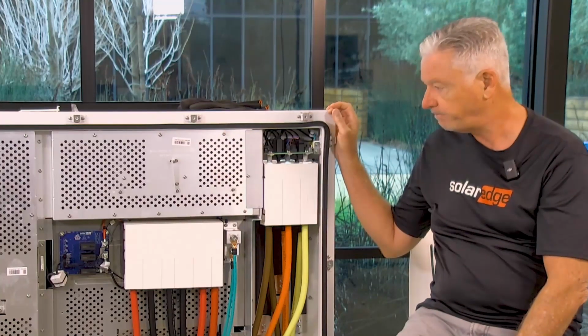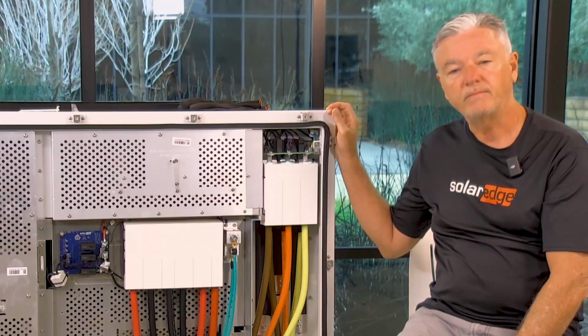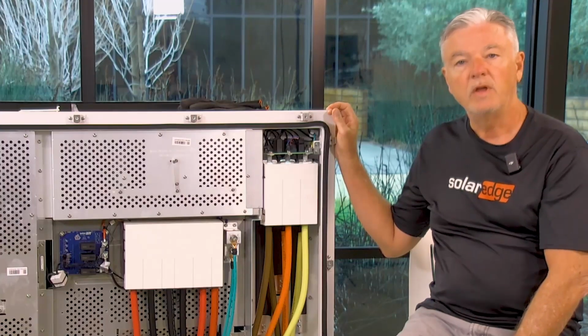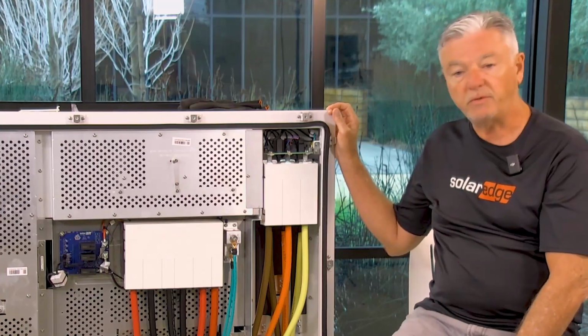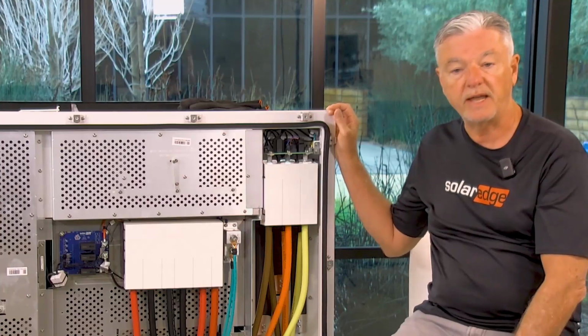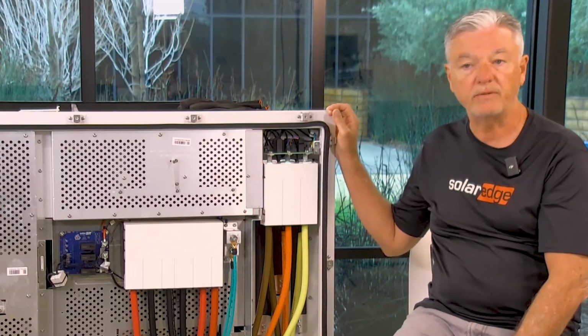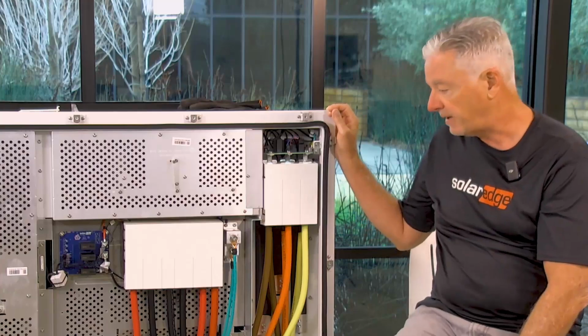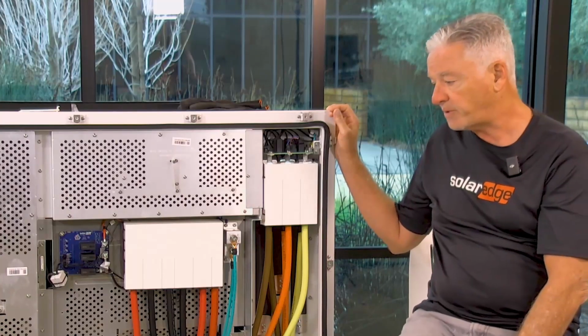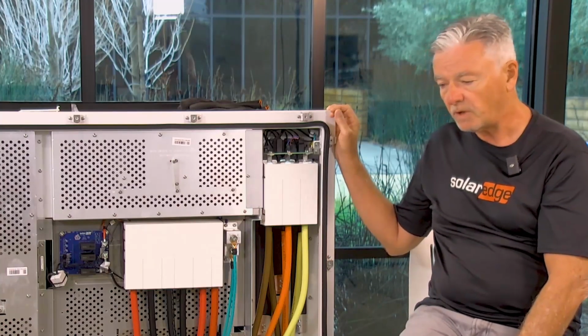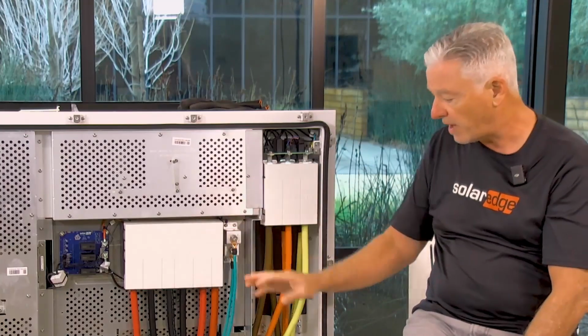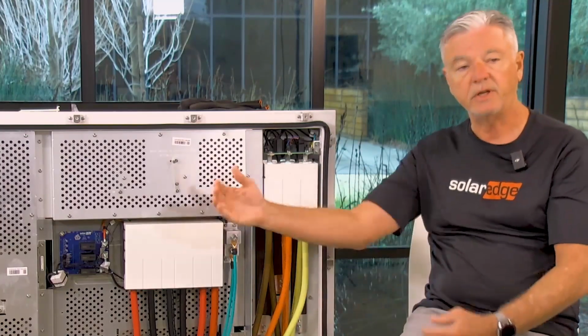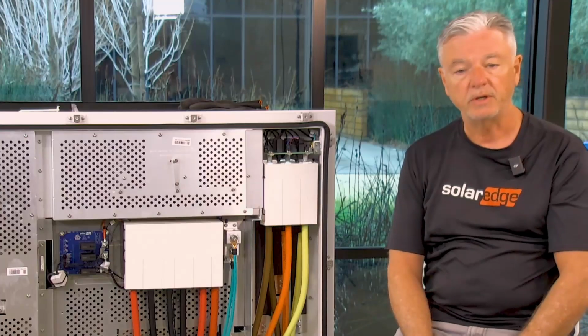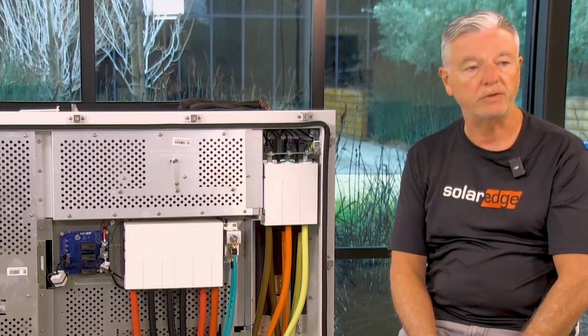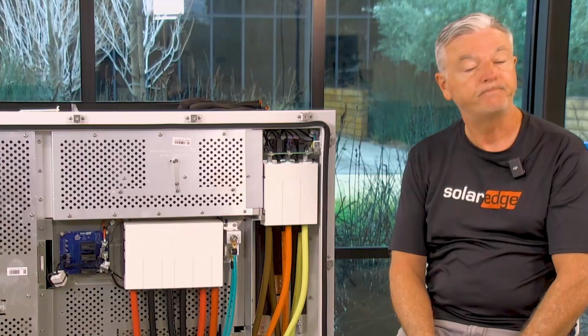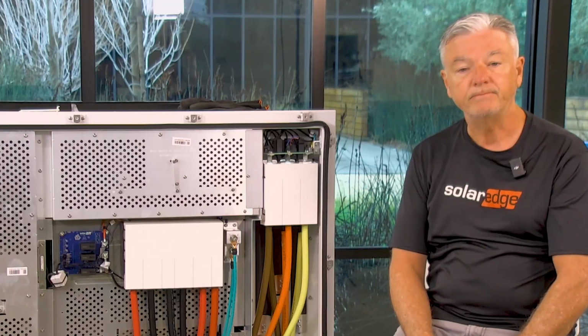Okay. Can you tell me any more about inverter to inverter comms? What is CAN? Yes, so the inverters speak to each other using a protocol called CAN bus. It's been around for a while in the automotive industry. It's highly reliable. So there's no special consideration for CAN bus. It's just the inverter to inverter wiring on the communications card. We also have the external RS-485 communications that you would normally use with external devices. Very good. All right, next up.